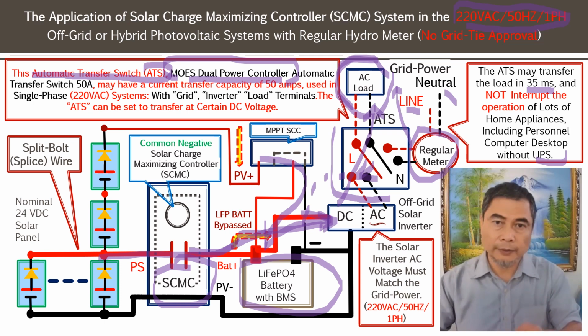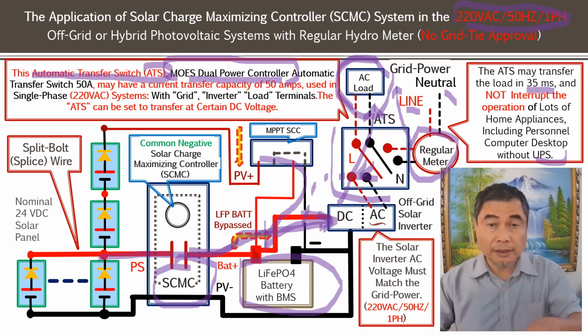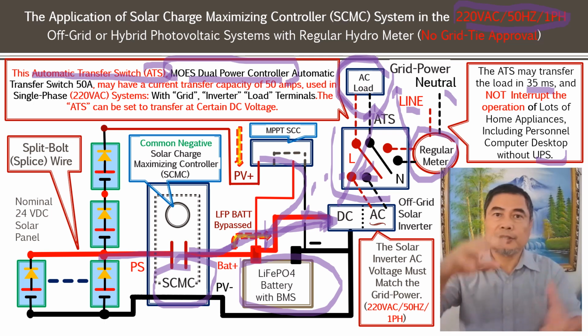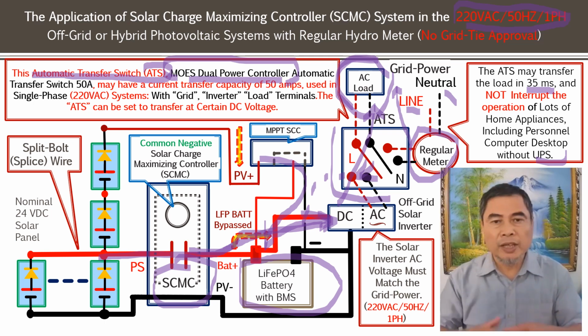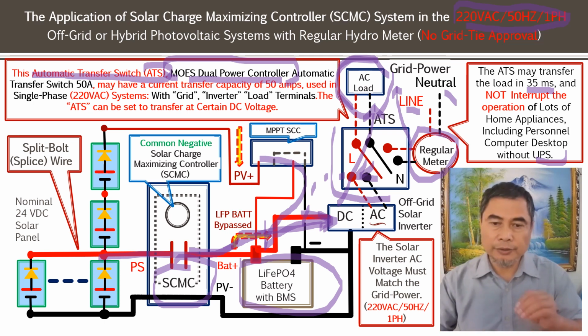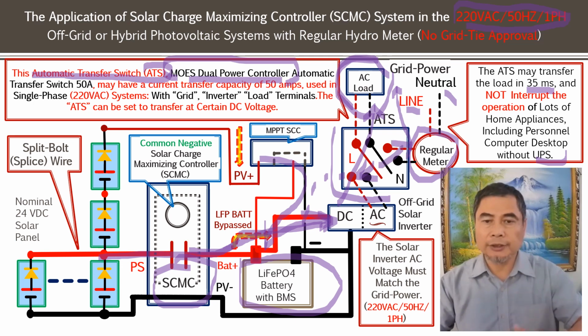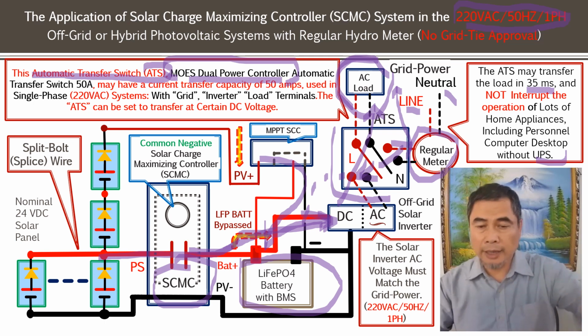When the system voltage drops to the 20% mark, you have 80% of the range to play with. Once it drops down to the 20% mark, which is 25.6 volts, and you set them to cut out, this switch will fall back to the grid.